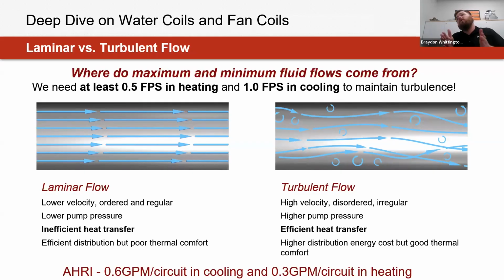Commonly, if you're dealing with much lower flow applications, a lot of the time you're going to see these software programs give you a warning or an error message. The reason is that they're trying to get you within that turbulent flow range. As we get below that, sure, we can extrapolate or interpolate some values, but it might not be exactly what's actually happening at that coil, as it's much harder to evaluate the laminar flow range.